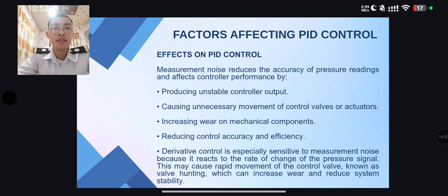And for the derivative, it is especially sensitive to measurement noise because it reacts to the rate of change of the pressure signal. This may cause rapid movement of the control valve known as valve hunting, which can increase wear and reduce system stability. The controller may continuously adjust the control valve even though the process pressure has not actually changed.